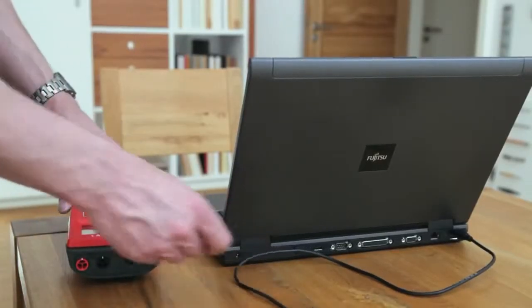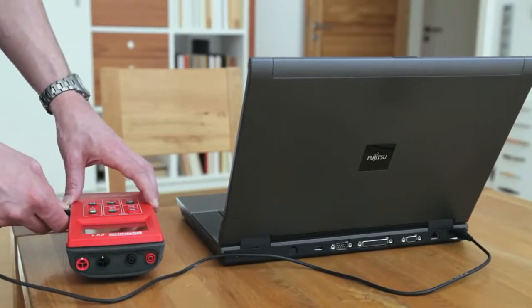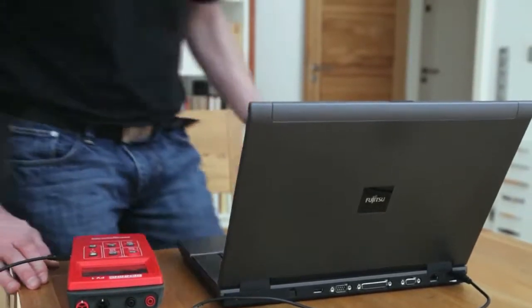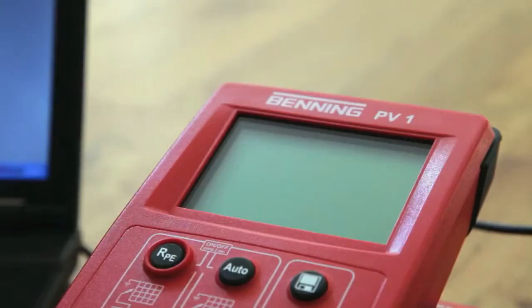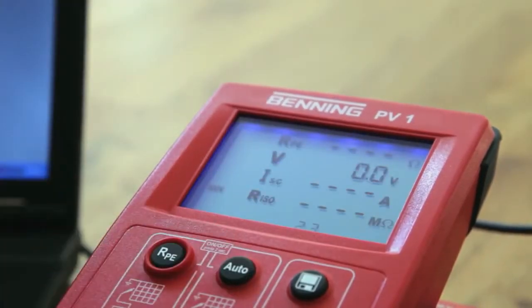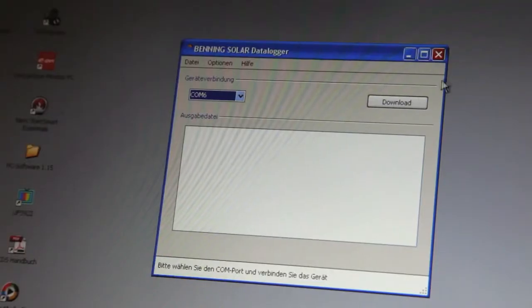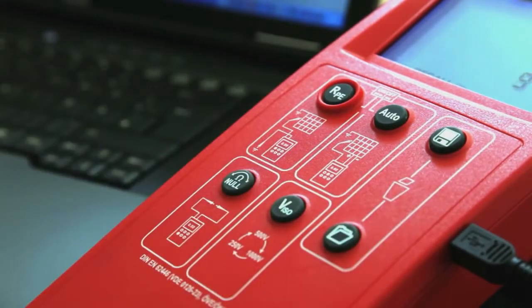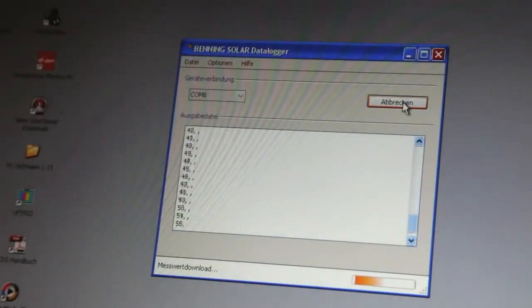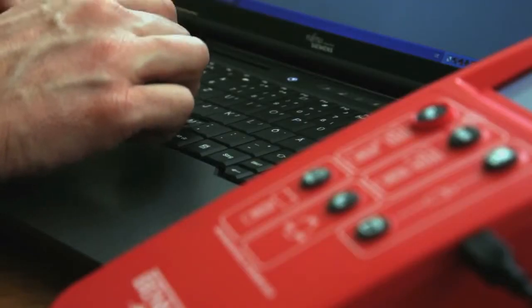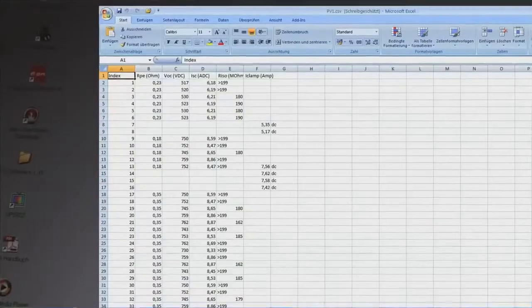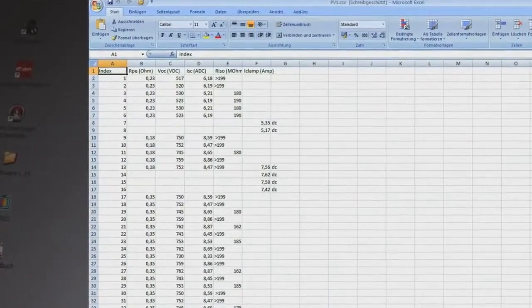The measured data stored in the memory of the Benning PV1 can be read out via the USB port in order to compile test records. Switch the Benning PV1 on and start the enclosed Solar Data Logger software. After pressing the Recall key of the device, the data will be transferred automatically to your PC. The data transferred can be stored in the CSV or text format for further processing, for example in Microsoft Excel.